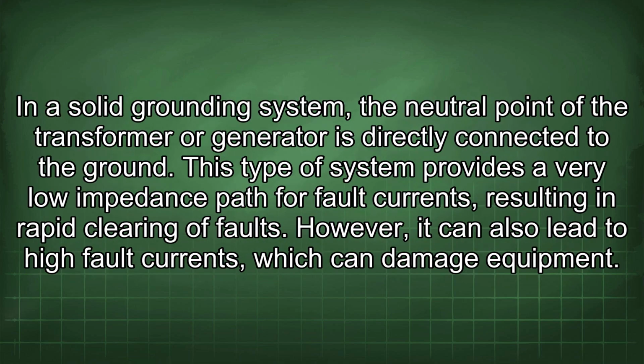In a solid grounding system, the neutral point of the transformer or generator is directly connected to the ground. This type of system provides a very low impedance path for fault currents, resulting in rapid clearing of faults. However, it can also lead to high fault currents, which can damage equipment.